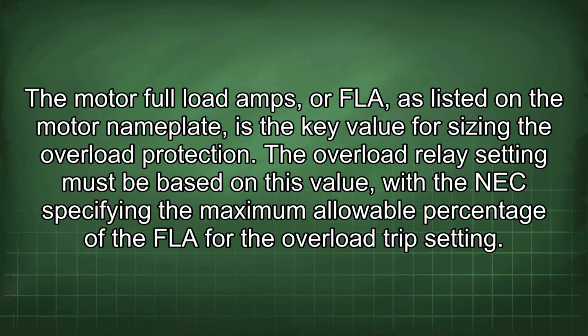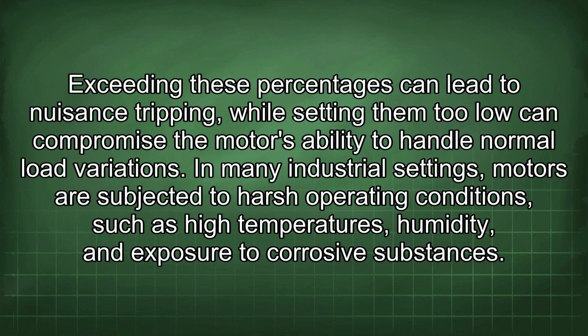The motor full load amps, or FLA, as listed on the motor nameplate, is the key value for sizing the overload protection. The overload relay setting must be based on this value, with the NEC specifying the maximum allowable percentage of the FLA for the overload trip setting.